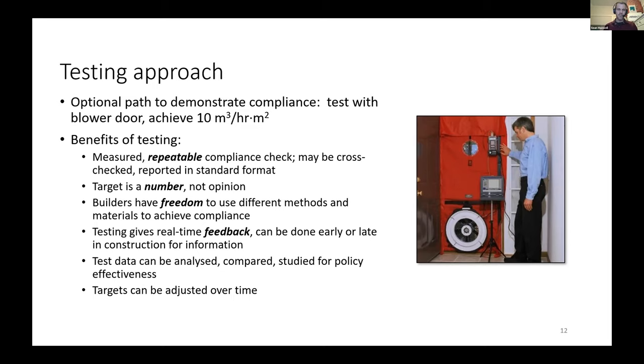The other good thing is that builders have freedom to use different means to get to that number that they need to meet. And testing itself, when you do a blower door test, puts pressure on the building, and that gives real-time feedback to the testers about which things are leaking and which things are not. So it's a pretty powerful learning tool. And for policymakers, it's also really powerful because those numbers can be adjusted over time. The stringency can be dialed up and dialed down, which you can't really do with an opinion-based verification strategy.